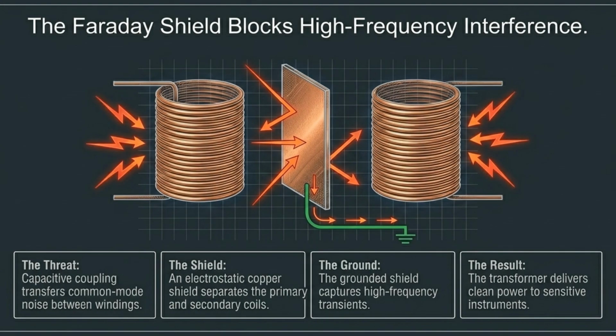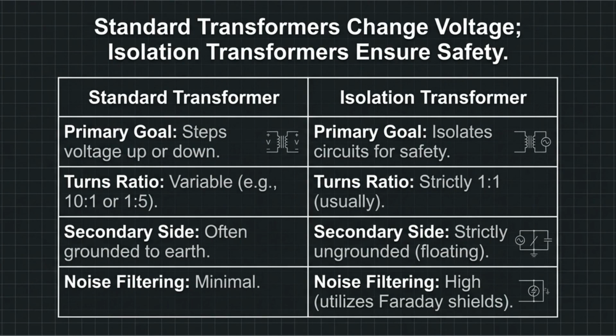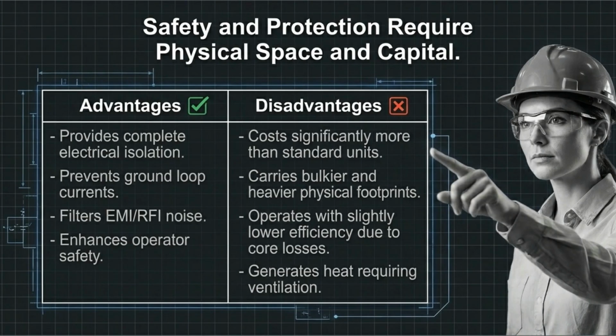A Faraday shield blocks high-frequency interference. Capacitive coupling causes common mode noise, but the grounded copper shield captures these high-frequency transients. The result is clean power delivery to sensitive instruments. Standard transformers primarily change voltage with a variable turns ratio and often have a grounded secondary. In contrast, isolation transformers ensure safety by isolating circuits, maintaining a strictly 1-to-1 ratio, using an ungrounded secondary, and providing high noise filtering. Isolation transformers offer complete electrical isolation, prevent ground loops, and enhance operator safety.